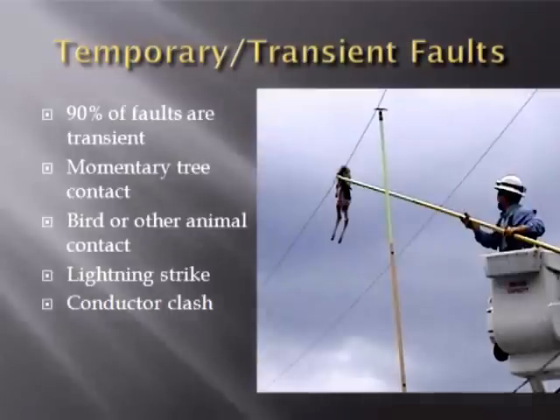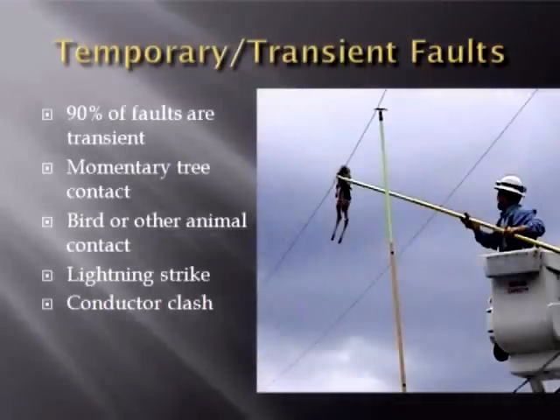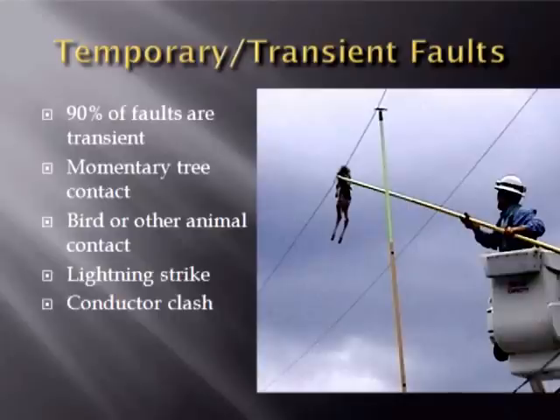A transient fault is a fault that is no longer present if power is disconnected for a short time. Many faults in overhead power lines are transient in nature. At the occurrence of a fault, the power system protection operates to isolate the area of the fault. A transient fault will then clear and the power line can be returned to service. Typical examples of transient faults include momentary tree contact, bird or other animal contact, lightning strike, and conductor clash.